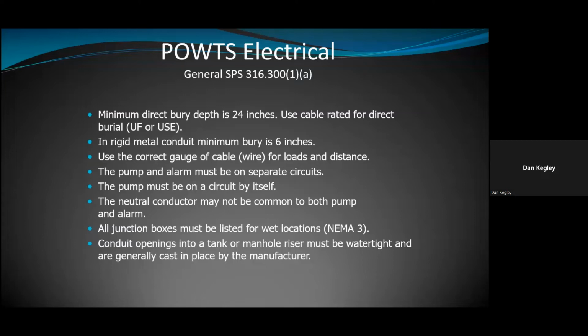The 3% voltage drop really doesn't apply to that because there's really no load there, because you're just closing a circuit to create a voltage circuit path to create the circuit to know that something's going on there. So that's why you can get away with kind of the lower voltage 2-wire, 3-wire cable out there.